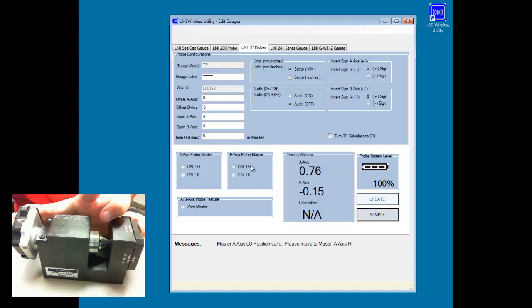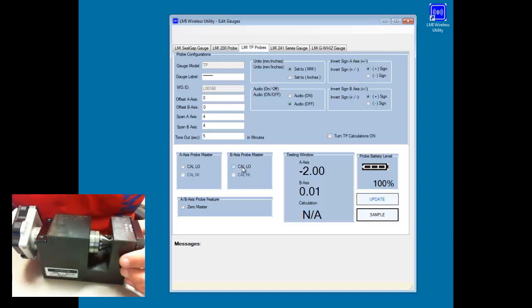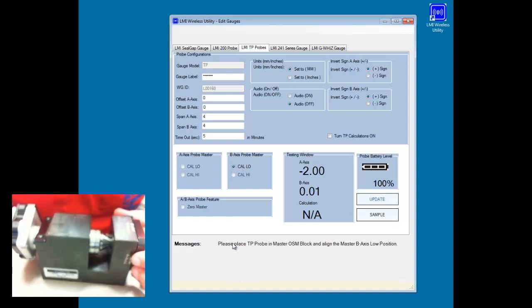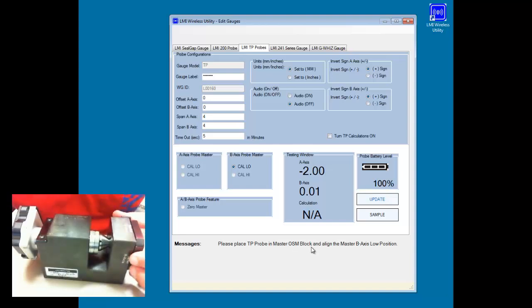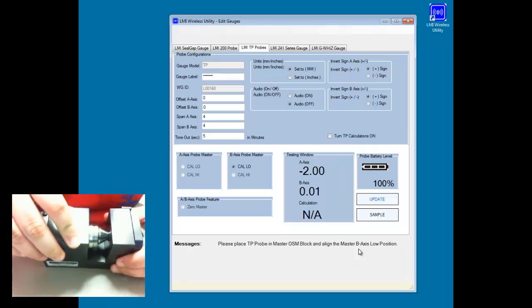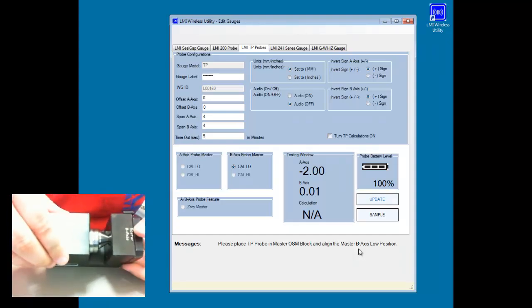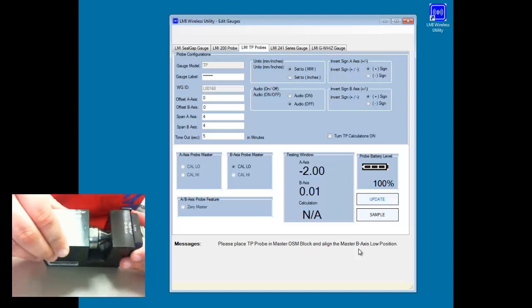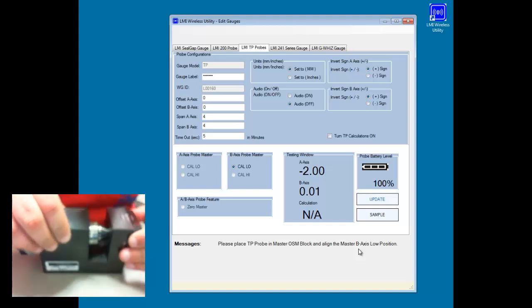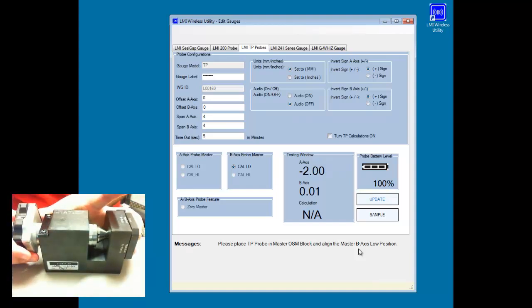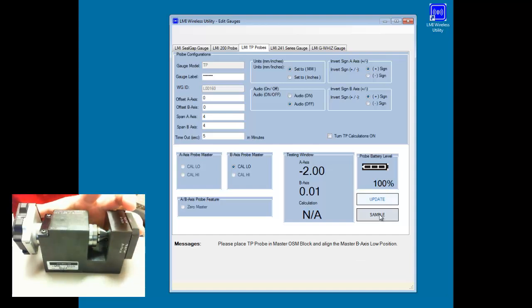So I click on the cal low button for this. It's telling me to please place the probe in the master OSM block and align the master B axis to the low position. So my B axis is up on the top here. I'm going to take this and rotate it. I'm going to make sure the probe is in there all the way. Hit the sample key.